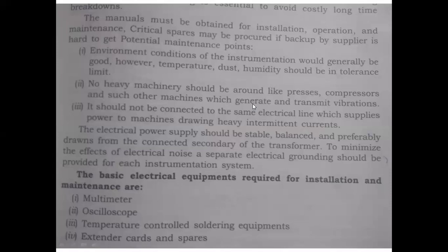If we connect these heavy machines near our operating equipment, the current flowing through the supply to the heavy machinery will also interrupt the operation of the operation theater. That's why most of the heavy machines and compressors are placed far away from the intensive care unit.